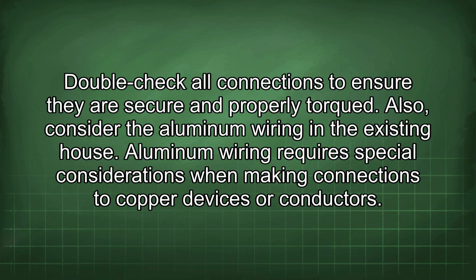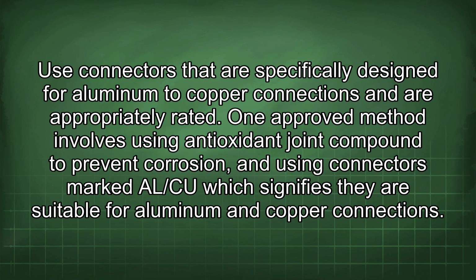Also, consider the aluminum wiring in the existing house. Aluminum wiring requires special considerations when making connections to copper devices or conductors. Use connectors that are specifically designed for aluminum to copper connections and are appropriately rated. One approved method involves using antioxidant joint compound to prevent corrosion, and using connectors marked AL/CU, which signifies they are suitable for aluminum and copper connections.